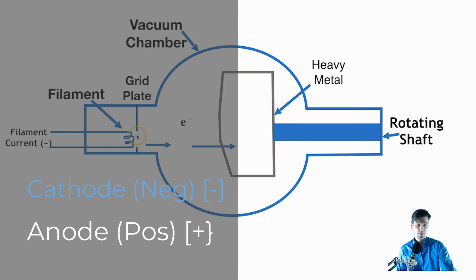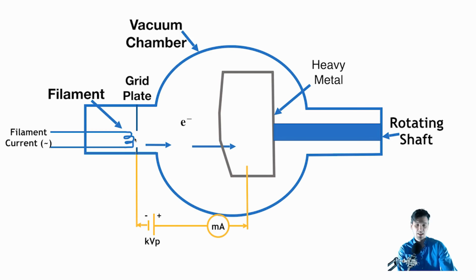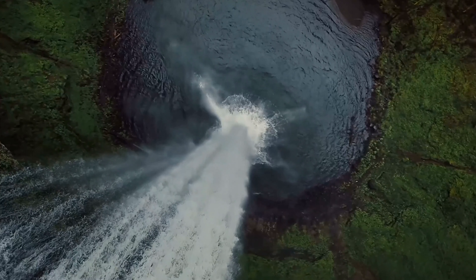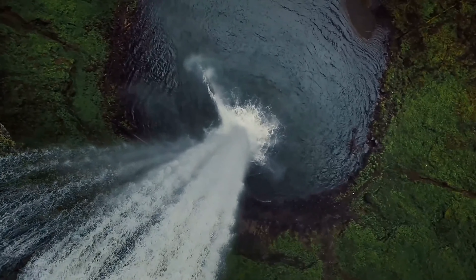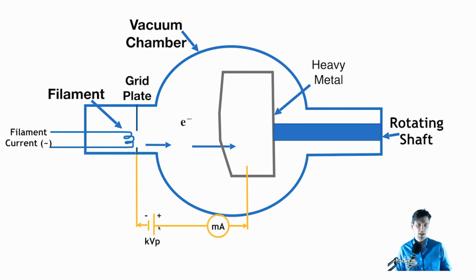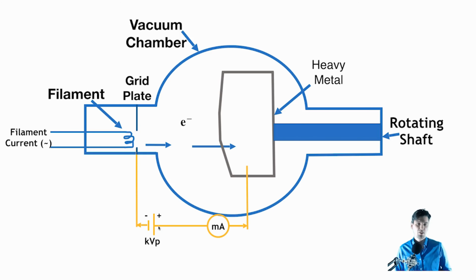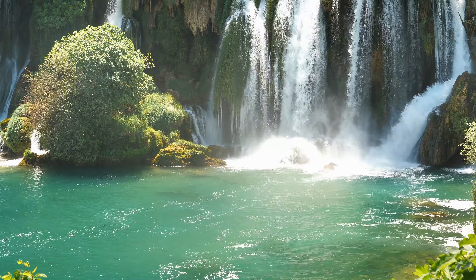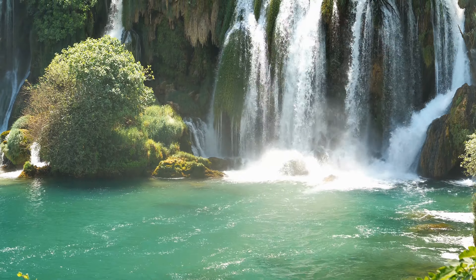This is also called the cathode, where the electrons come out. The electrons are negative and they want to flow towards a positive. That potential across there is called the KVP. The KVP is just like a potential in a battery — or using a waterfall analogy, the height of the waterfall is the potential that water has at the top of the waterfall. Similarly, KVP is the potential difference between the cathode and the anode. The mA, or milliampere, has to do with how many electrons are passing through — it's the measure of the current.